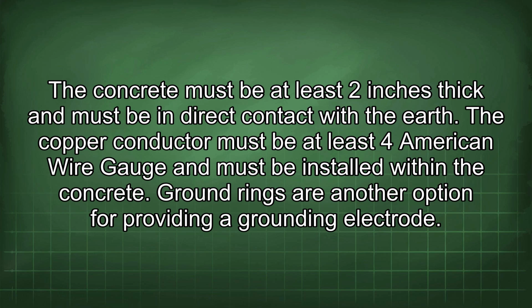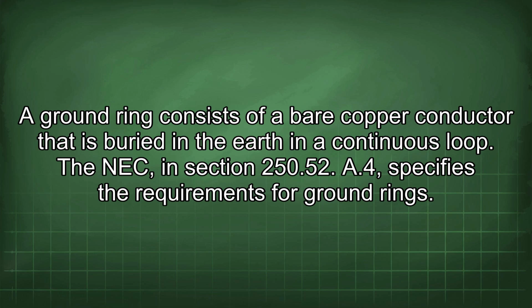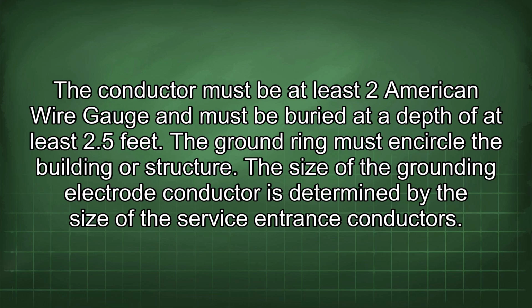Ground rings are another option for providing a grounding electrode. A ground ring consists of a bare copper conductor that is buried in the earth in a continuous loop. The NEC in section 250.52(A)(4) specifies the requirements for ground rings. The conductor must be at least 2 American wire gauge and must be buried at a depth of at least 2.5 feet. The ground ring must encircle the building or structure.